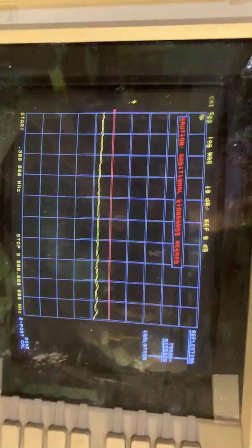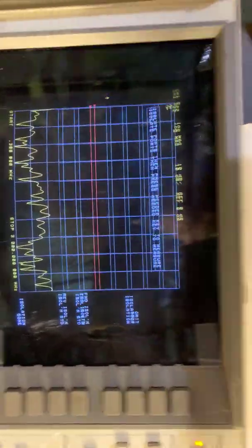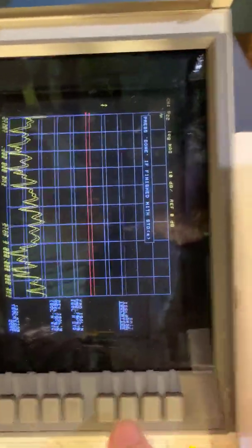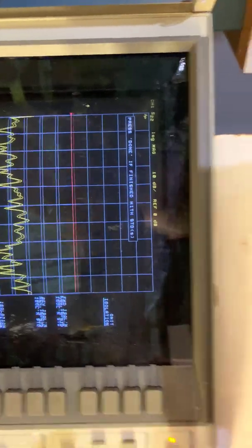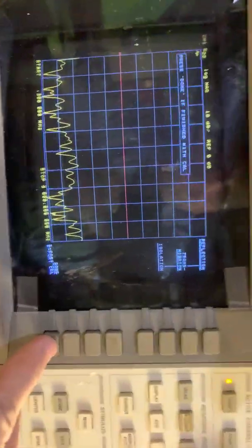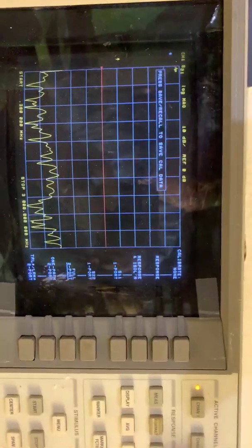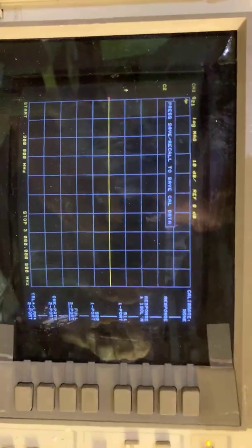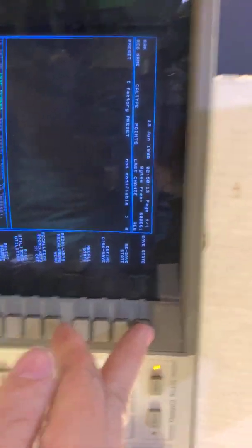One little piece of information I forgot here, we actually have to press isolation and then click omit isolation for this firmware revision. It won't let me just skip it. Okay, so now we got all this highlighted here. We press done, and so press save, recall the save cal data. So we're gonna press save, and we're gonna press save state, and so now we're done.